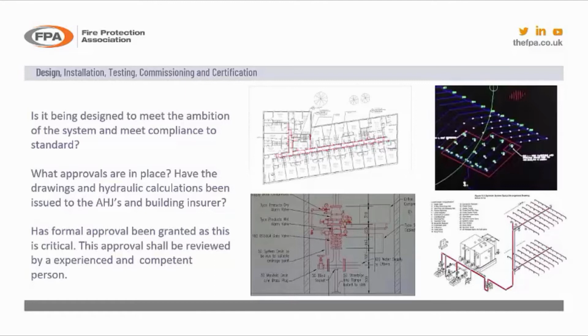Unfortunately, this is a process over the years that I've been involved with sprinklers, which is over 30 years, that has lapsed, so to speak. 30 years ago, the most important process was you sent the drawings off as soon as they were complete to the insurer for approval, and you couldn't order a sprinkler pipe or a sprinkler head until you'd had written approval, or you had some form of granted approval subject to site survey before you could go into fabrication of a sprinkler system. It's a critical process, and like I say, it's now been missed, and it leads to awkward questions and queries later in the project when non-compliances are witnessed.